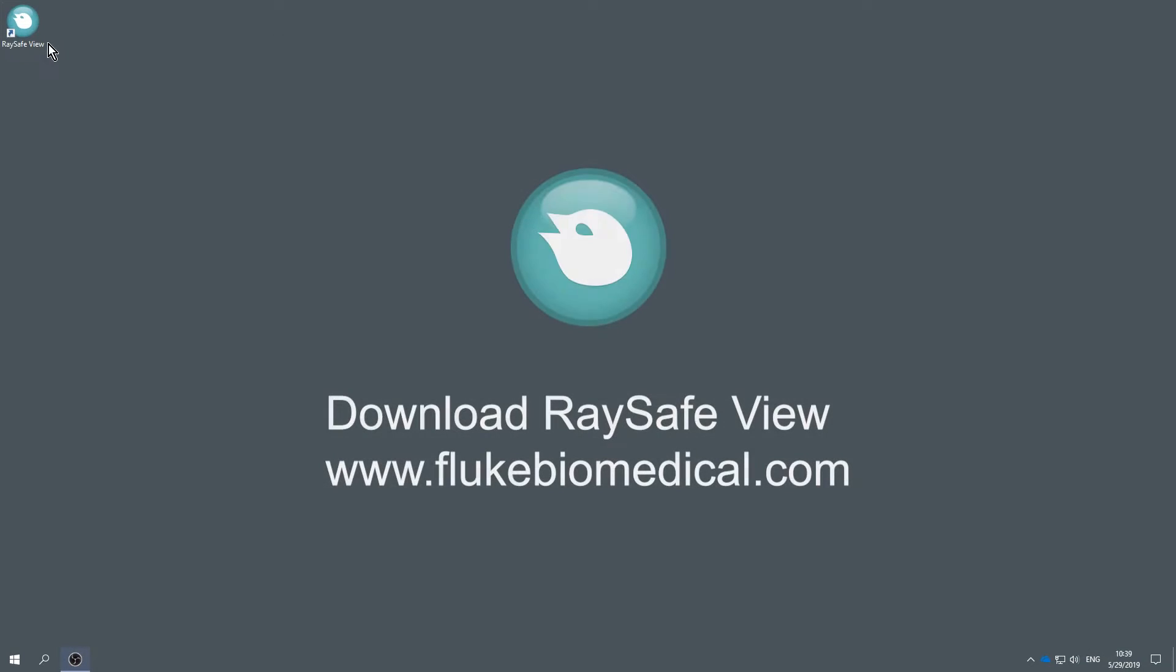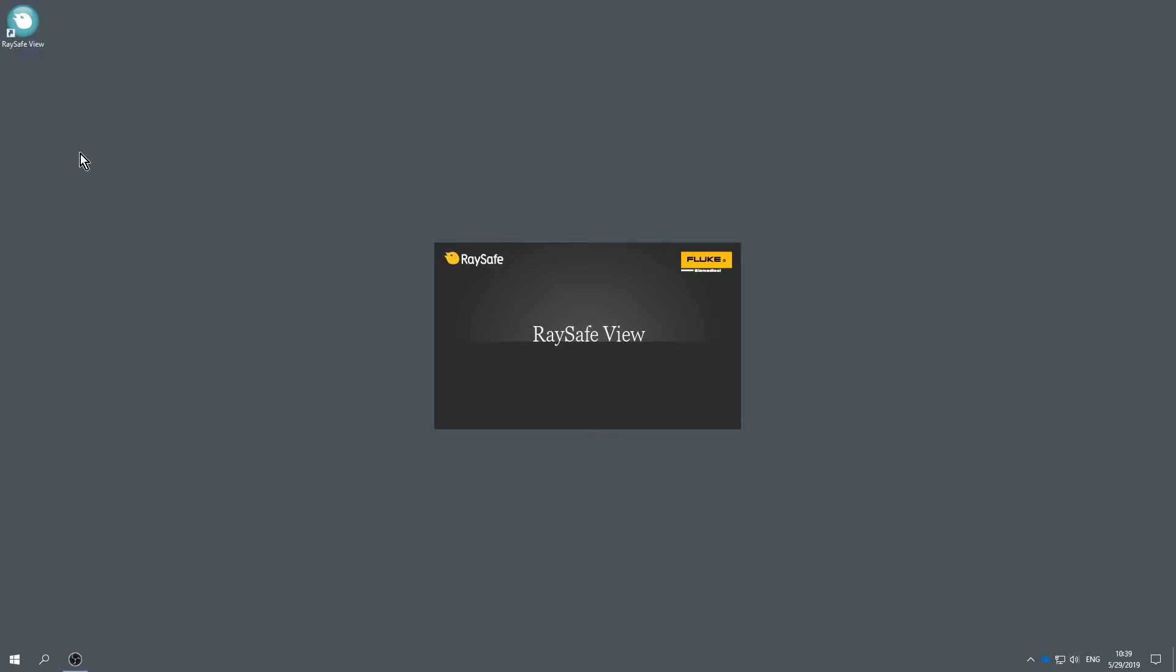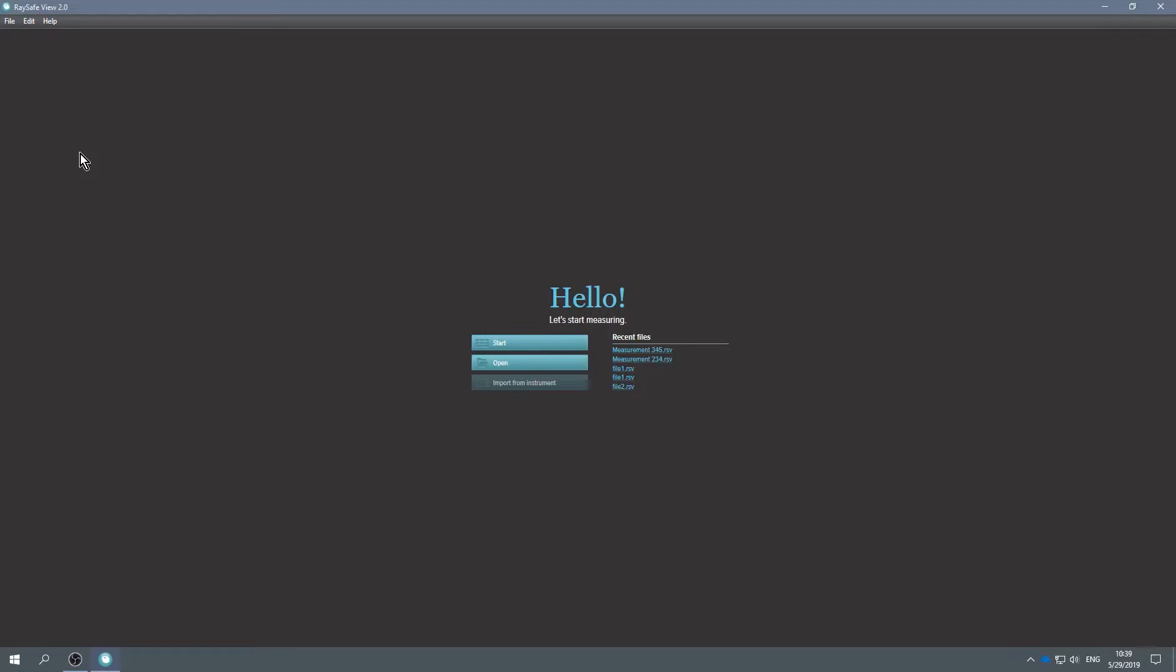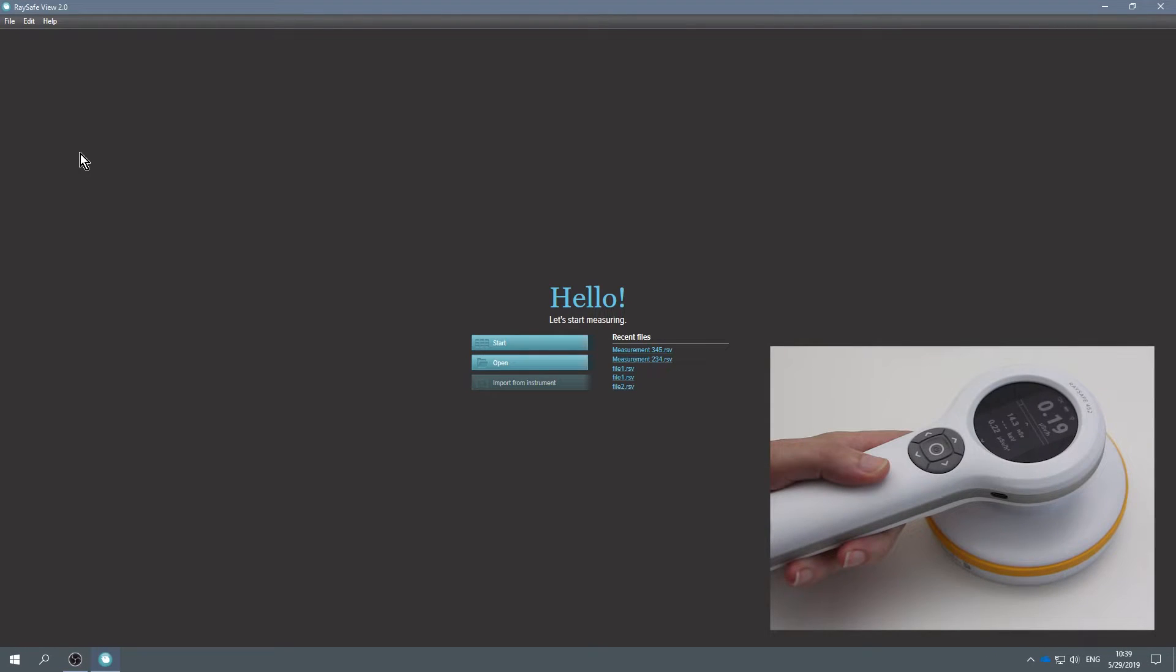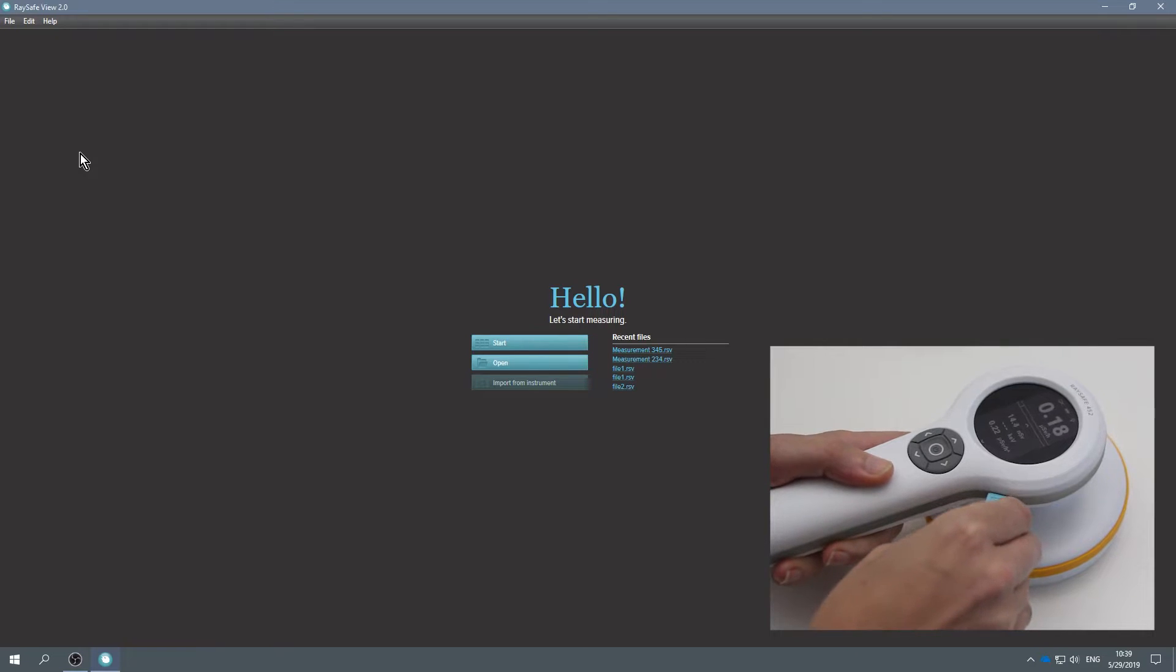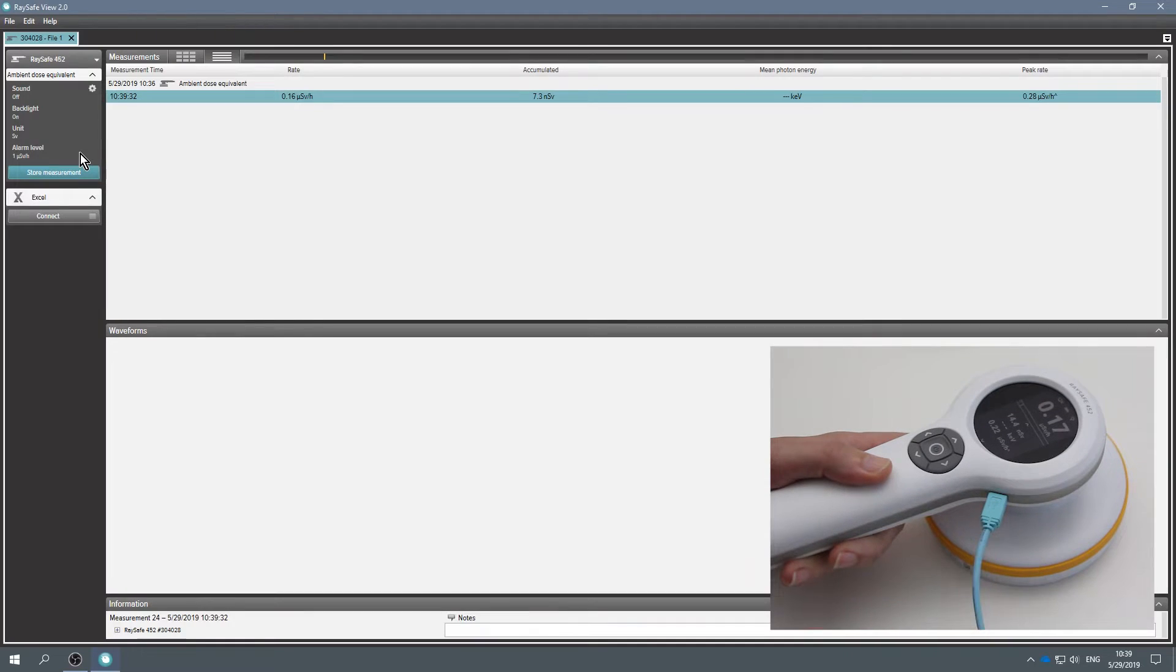If you want to view older measurements, you use the PC software RaySafe View. Start RaySafe View. The RaySafe 452 comes with a USB cable. Connect the cable and now live measurements will appear in RaySafe View.